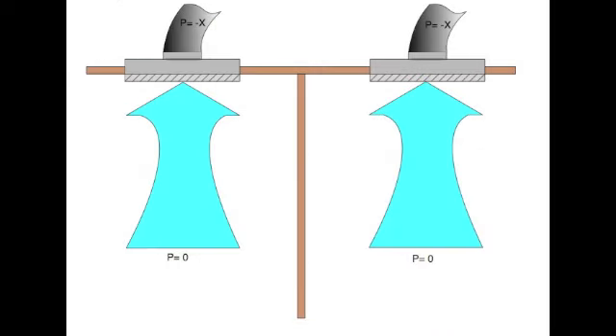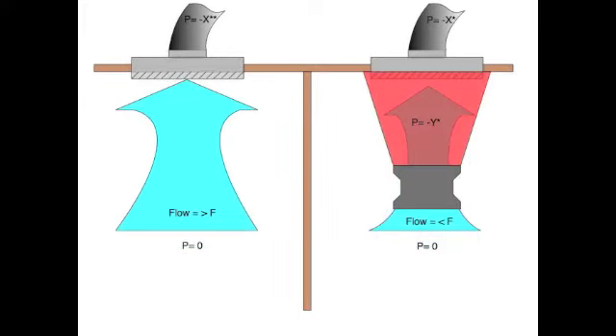One of the big challenges of measuring system air flow at return grills is on systems with more than one return. The pressure and flow at one return can easily be affected by factors at the other return grill. Any measurement tool that restricts airflow will cause the air to shift to the other returns, unless multiple tools are used to measure all returns simultaneously.